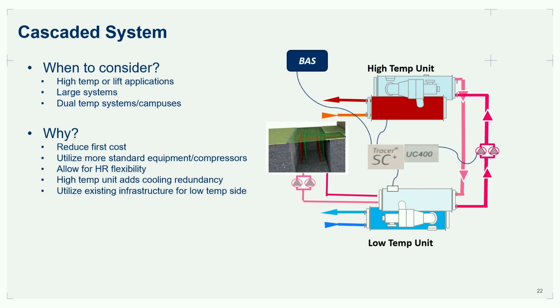So often on these electrification jobs, the dollar values just get way too high and the job just falls dead in the water, unless there's obviously significant regulation forcing you to do that. But for the people that want to, that first cost barrier is a major barrier to overcome to make jobs happen. So we're able to utilize more standard compressors that our technicians know and love. It's coming off of standard manufacturing lines, and it costs a heck of a lot less than our specialized equipment that might be able to do 200 degrees of lift. Let's use that existing infrastructure, right? Let's not throw out those chillers. Let's use that to tack onto and achieve our high temp.